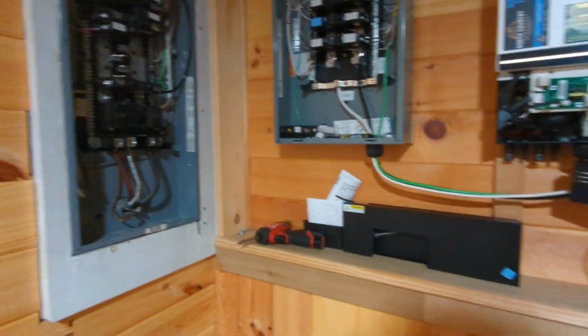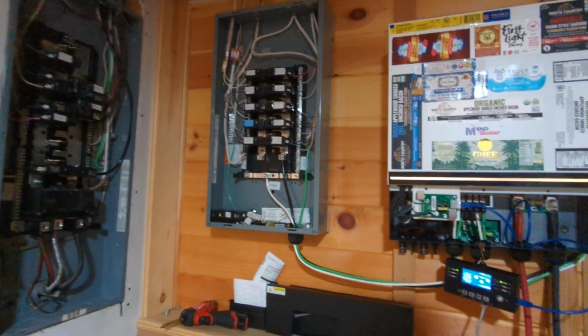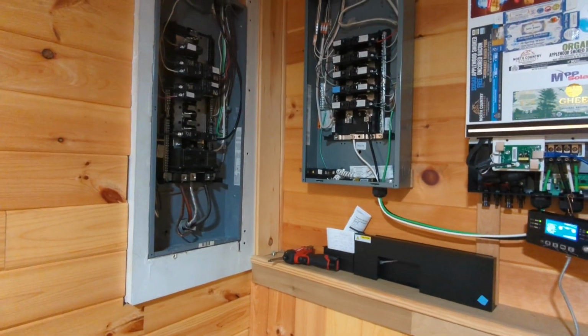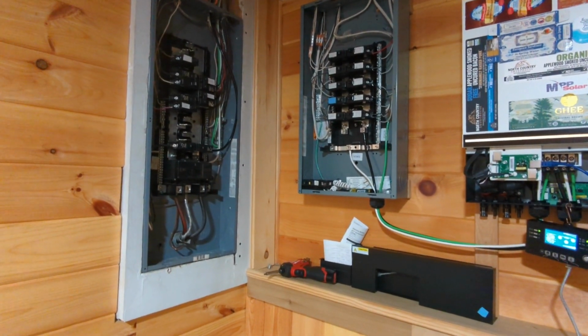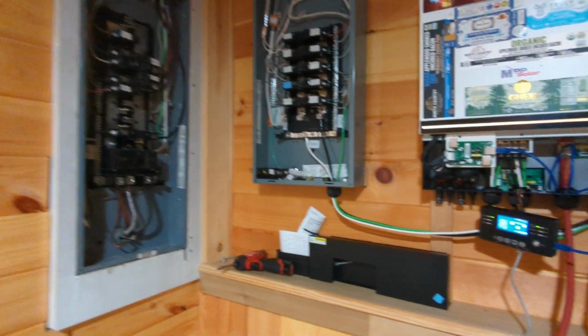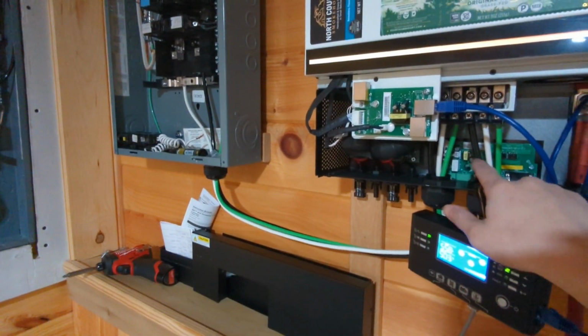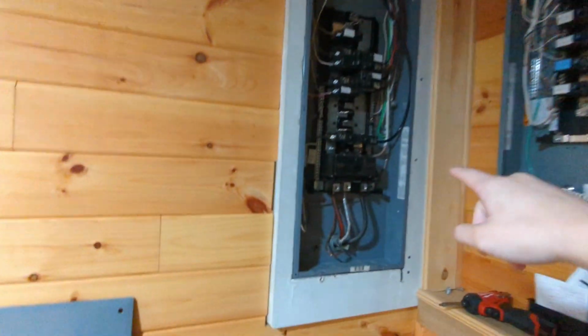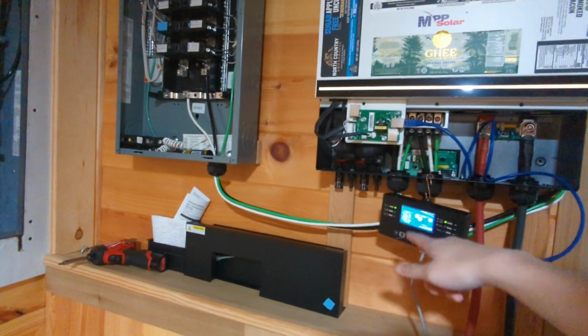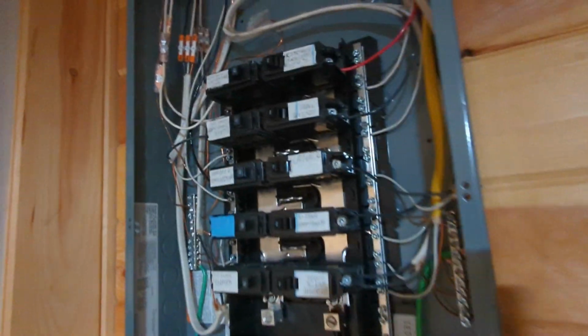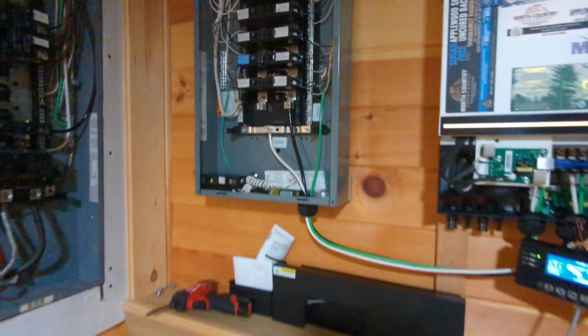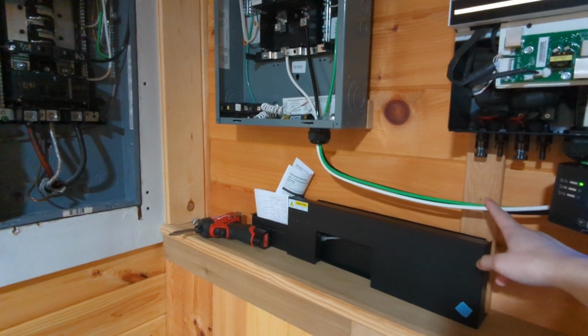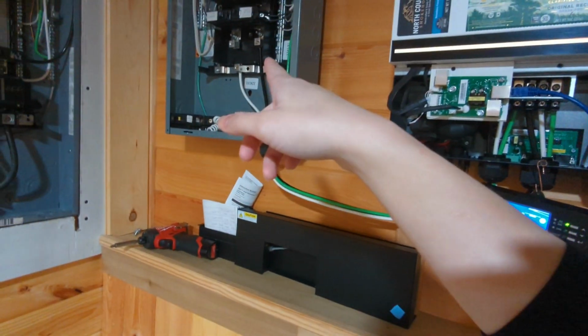So pretty much the way the inverter is connected between the two panels is I put this inverter in a grid down operating mode, so that's where the AC input to the inverter comes through the three wires on this side over here. They come up and over to the first panel. You can see the larger three wires, the larger 6 gauge and the 4 gauge, black, white, and green. Those wires go up and over, and they come over to the AC input of the inverter. And then of course the output of the AC inverter goes to all these 120 volt single pole breakers. They power all the 120 volt loads. This would be the wire that connects the output of the inverter to those breakers.